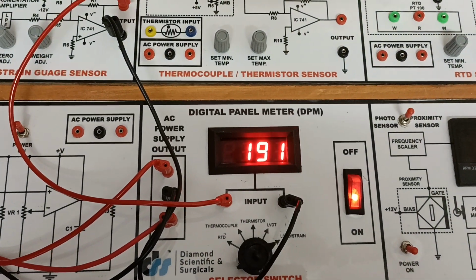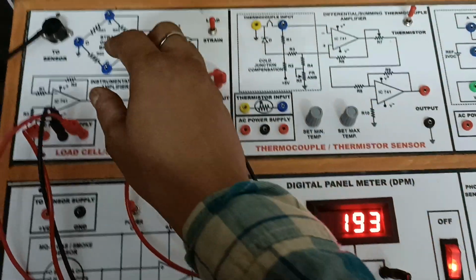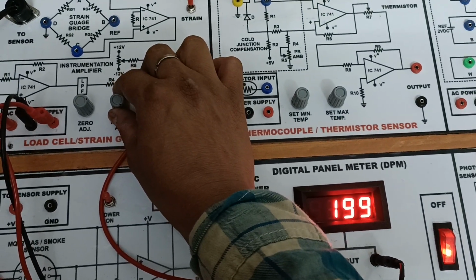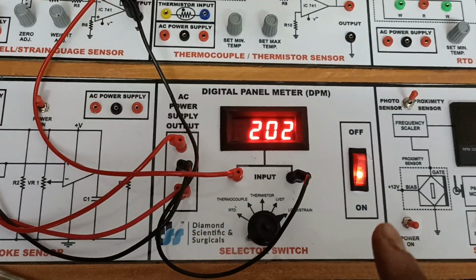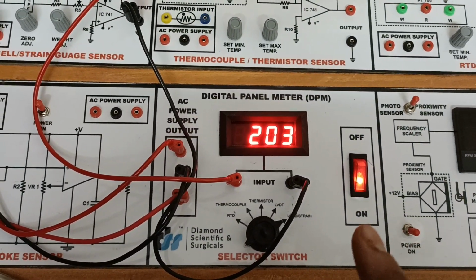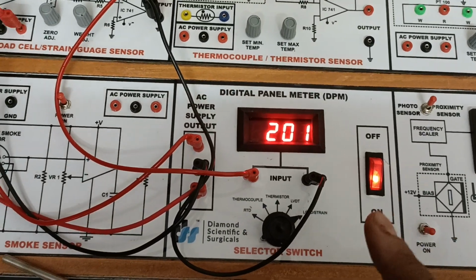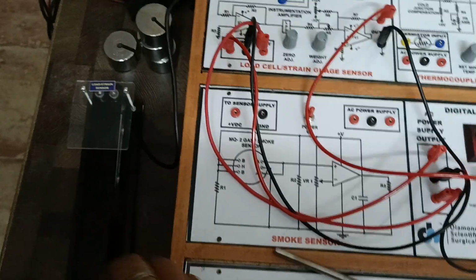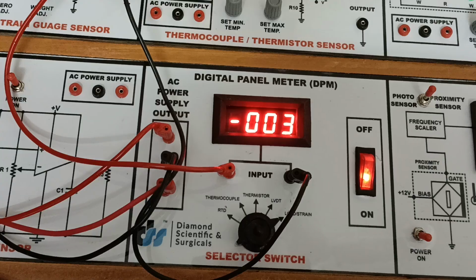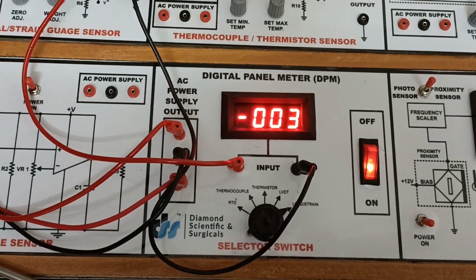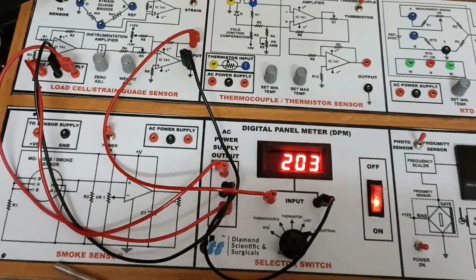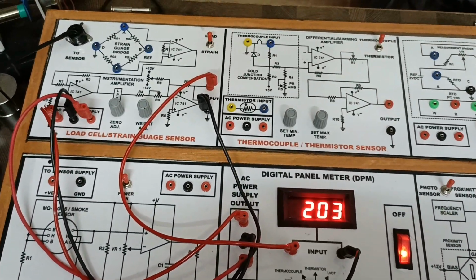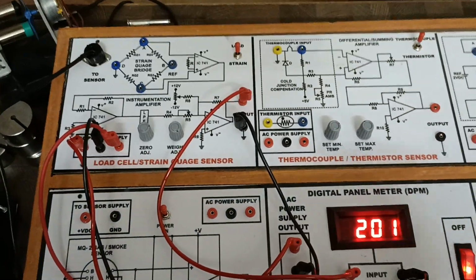If this reading is not accurate, you can select the weight adjust and set the 200-gram load on the DPM, and take off the weight, and the DPM shows 0 gram. You make these steps 2 or 3 times, and the sensor will be set.